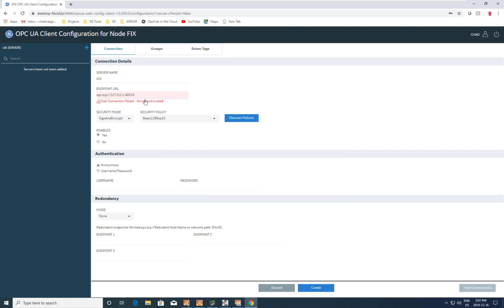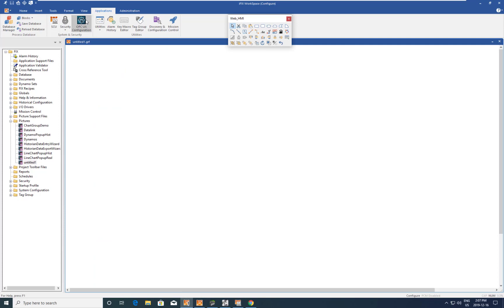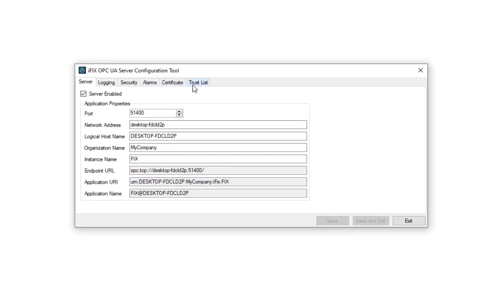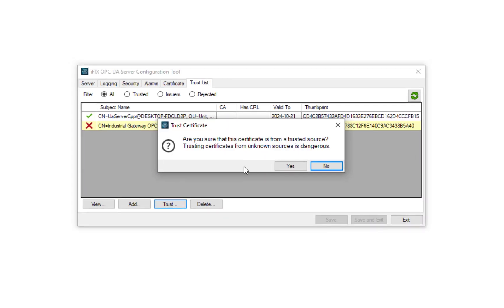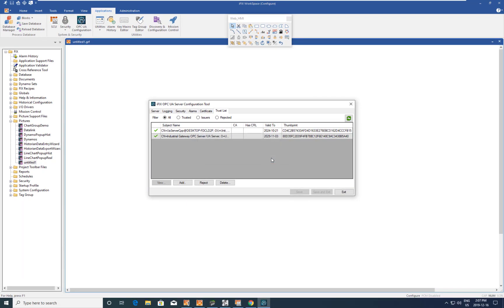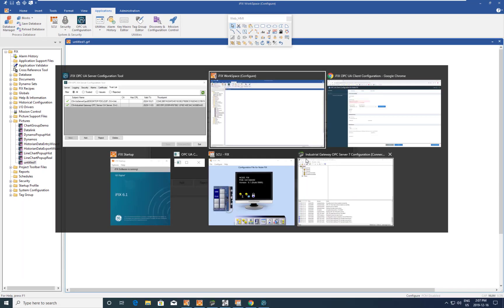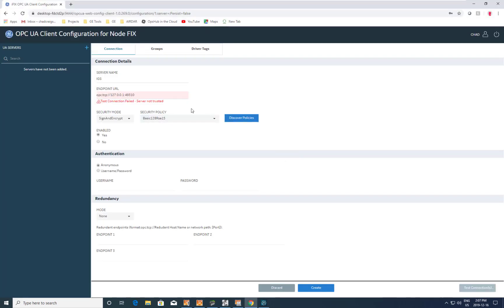Now we see that the server isn't trusted — the server trusts us, but we need to trust the server. So if we go back into iFix, open up the OPC UA configuration, and look at the trust list, we'll see that the IGS is in our untrusted list. We hit the trust button and now we trust the IGS OPC UA server. Technically now if we go back in here we should be trusted.